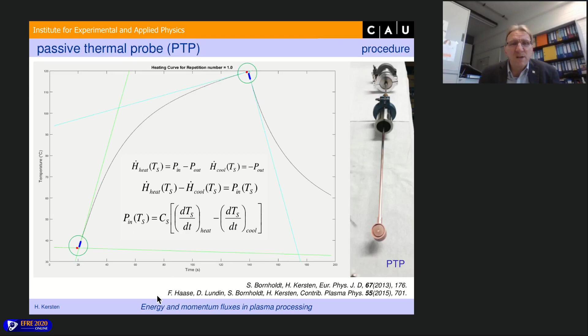You just have the heating of the probe and the cooling of the probe. And this is related to the time derivatives of the temperature during the heating phase and the cooling phase. You just have to have the derivatives here. Usually we take it here in the beginning of the process. And if you know the heat capacity of the probe, you have to know the heat capacity by calibration procedure, then by this simple formula, you get the integral energy flux. You get the integral energy flux measured by this probe. It's really very, very simple.